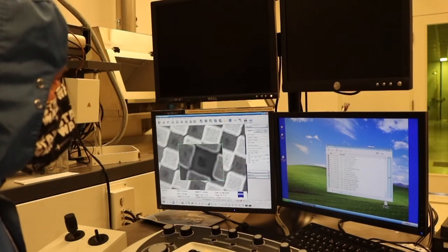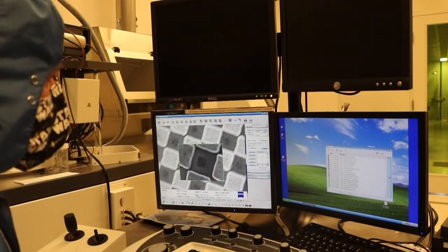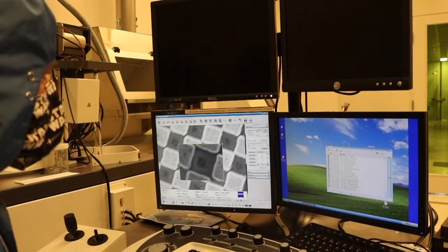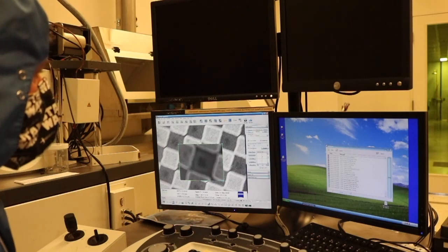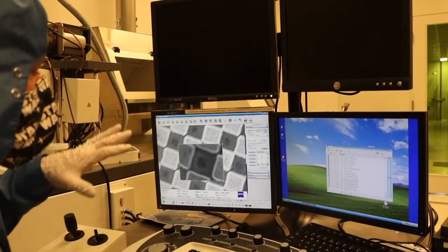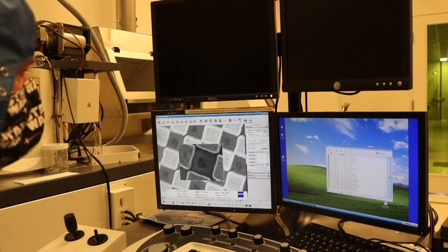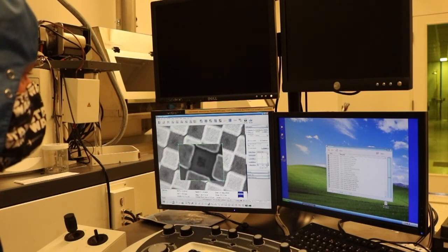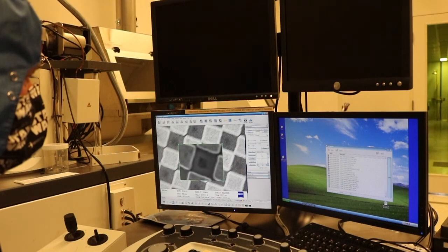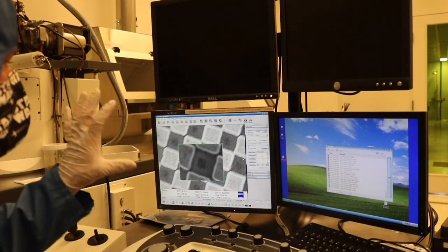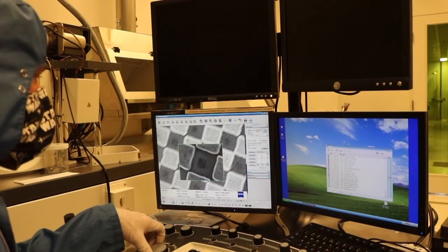If the little aperture window doesn't pop up, you can come straight to the apertures tab where you will have all the controls there. The amplitude control can be used to increase your amplitude depending on your magnification or decrease your amplitude. The higher the magnification, the less amplitude you should use to see the misalignment. Once the image is going perfectly in and out of focus, you can turn off the wobble.